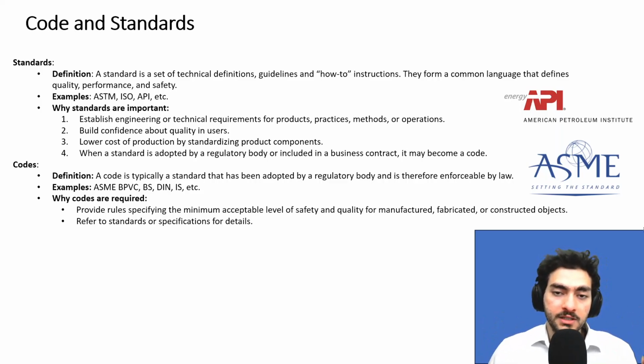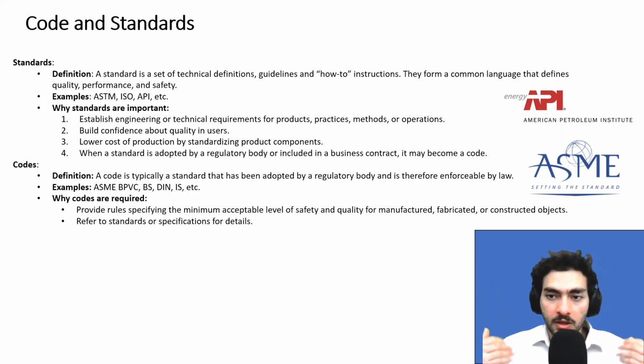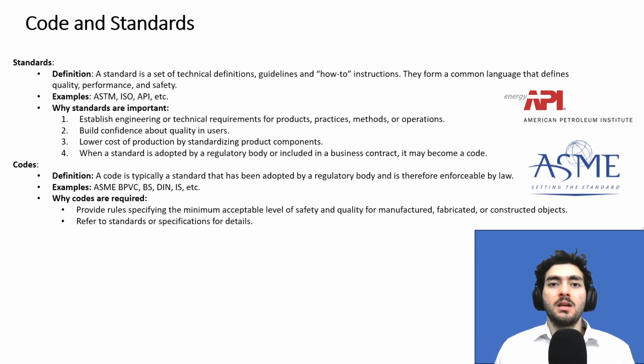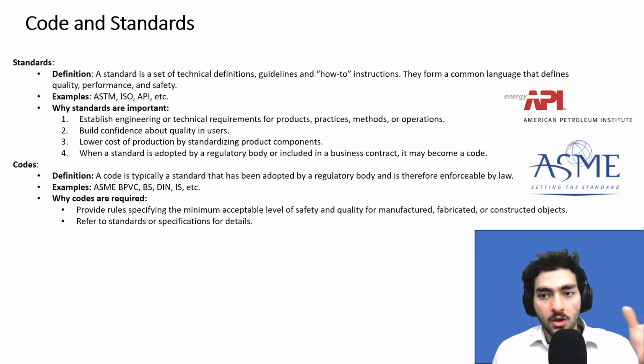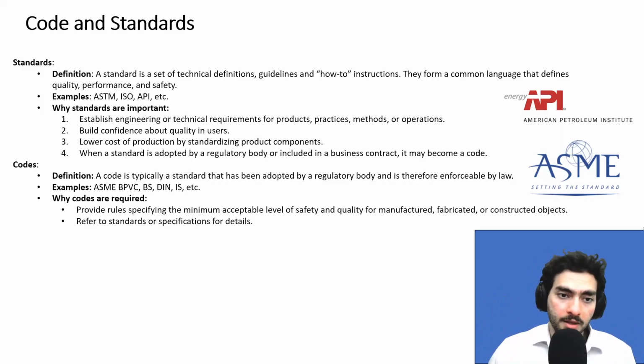So if you, for instance, purchase a pressure relief valve that follows the ASME code, and it has the ASME stamp, then that shows that this valve reaches the relieving capacity at the overpressure accepted by the code. Now, that doesn't stop you from adding instrumentation or other methods to make your system inherently safer, but if you want to follow the code, as a minimum, you must have a pressure relief valve on a vessel that follows a particular set of criteria, which we will cover, by the way.